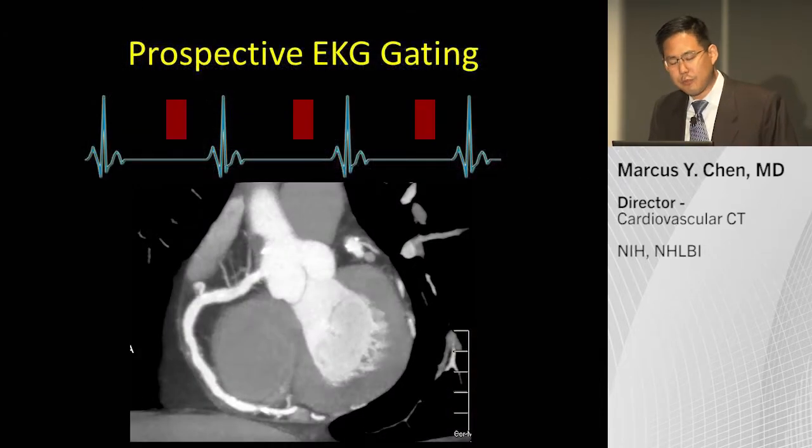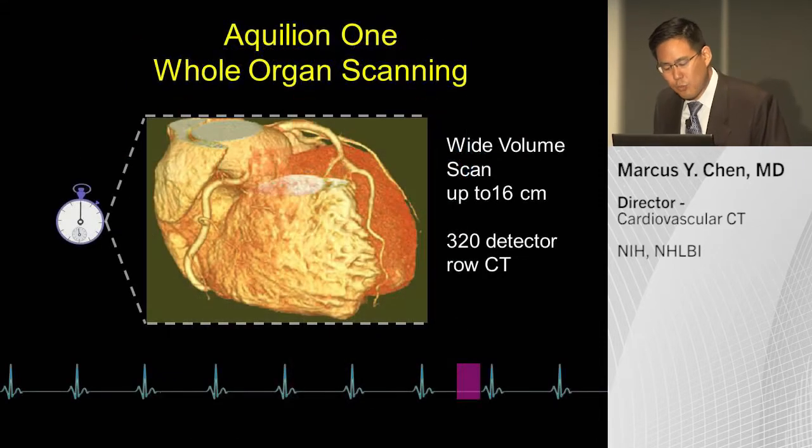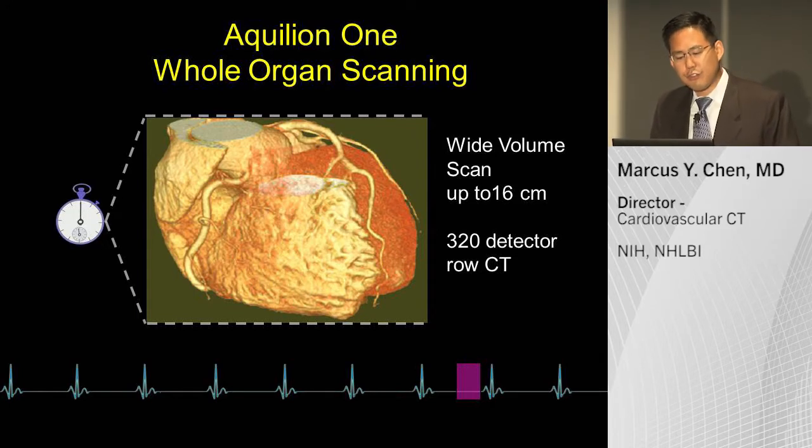Technology has evolved. We're now doing predominantly prospective ECG-gating to reduce the amount of radiation exposure. The newest technology, originally about five years ago with the Aquilion One, is whole organ scanning, where you have 320 detector rows and are able to image the heart within one heartbeat.